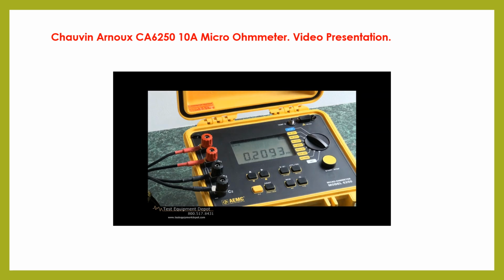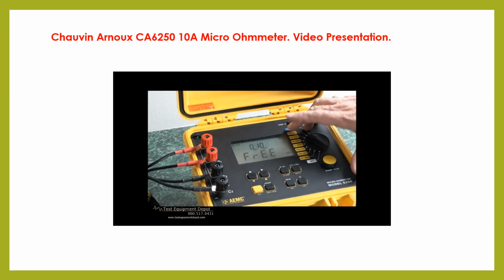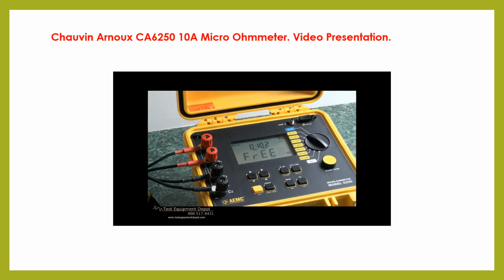So we see the sensitivity of this device as we increment up the scale, pump more current through, and increase sensitivity. Now at any point in time I can hit the mem button and store that, and again it will be object 1, test 2. My next test will increment to test 3, and so on. This instrument comes with a software package, which is the universal data view software that AEMC has that will operate across a broad spectrum of our test instruments.